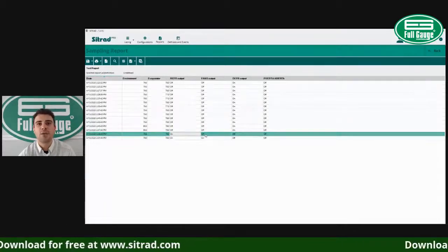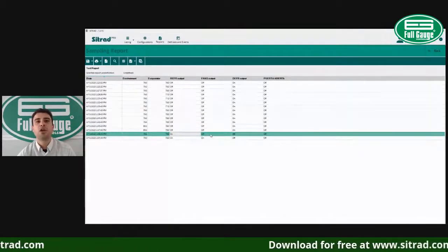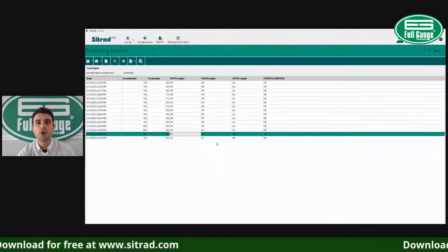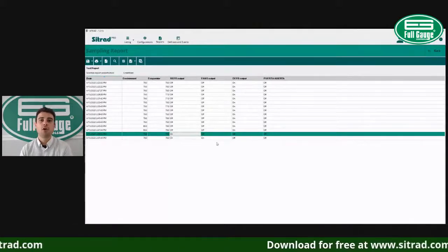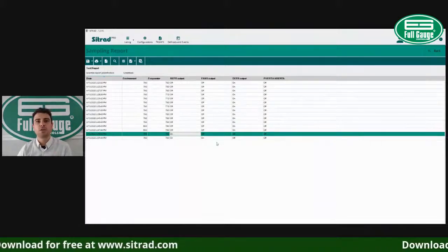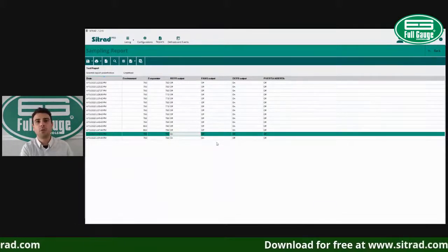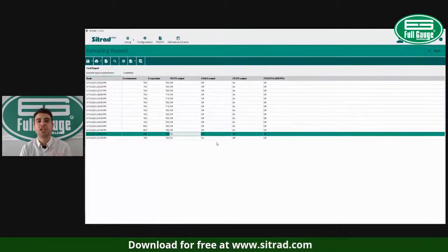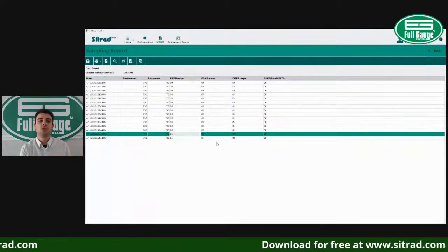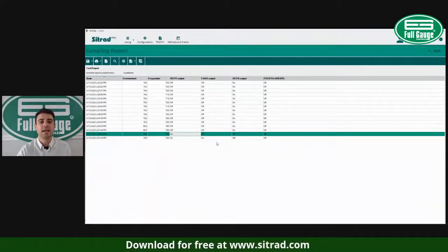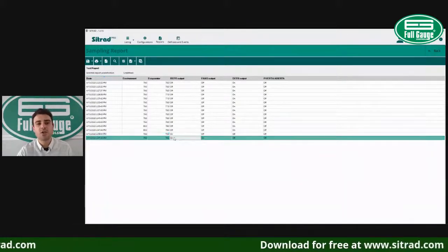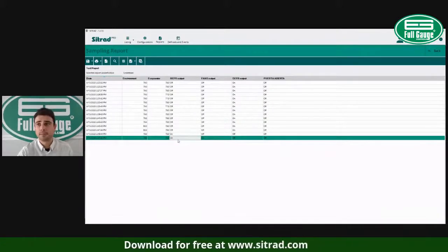Why are the fans off in this case? Because this is a freezer application. We want to cool down the coil. We want to drop the temperature of the coil before bringing the fan on. That way we will prevent the heat that was generated during the defrost cycle from being transferred from the coil to the room. So that's why we had the fan delay cycle. And once that fan delay cycle is gone, we have the compressor and fan working.